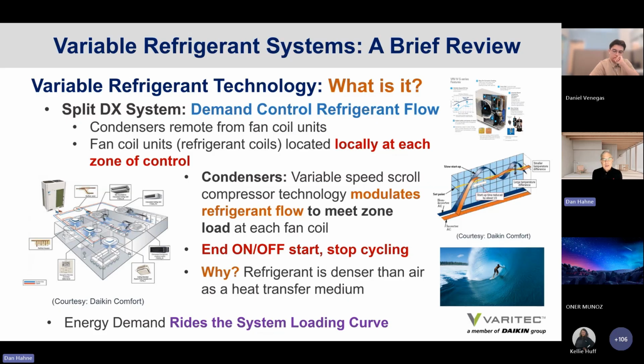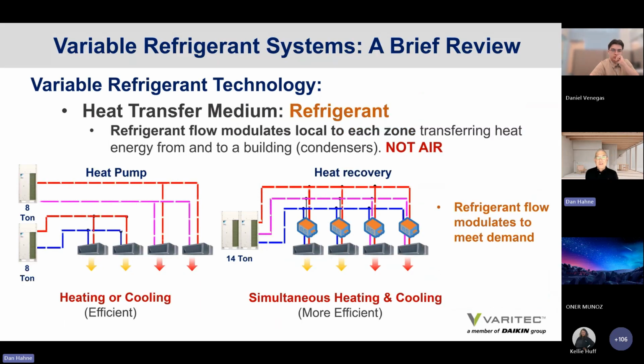So refrigerant flow is modulated based on demand, which means the compressors do not work 100% of the time. They modulate, and this removal of the on-off start-stop cycling sequence adds a lot of efficiency to a system. Systems are able to ride the heat load in a space. And here's a dynamic graphic illustrating the two types of variable refrigerant systems available. Heat pump systems, where condensers can either be in heating or cooling mode, serving all the independent zones associated with the indoor fan coil units, or they can be in heat recovery mode, where a single condenser can provide a means of simultaneous heating and cooling at each of the fan coils connected to that condenser.